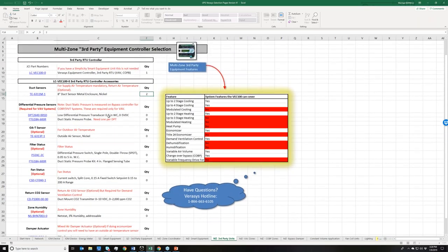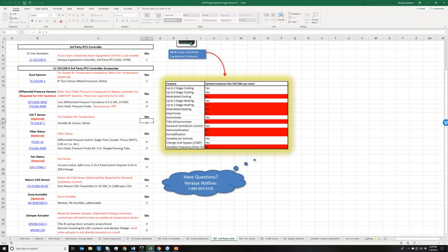Ducted pressure is measured at a bypass for a changeover bypass system with Verasys. So this is really only required for the controller if I'm doing a VAV system, because the changeover bypass system with Verasys can support both zone dampers and VAV boxes. I'm going to show an opportunity here using changeover bypass. Just note that if this was a VAV rooftop unit supporting VAV boxes with a drive on it, we would want to measure duct static pressure at this controller, and then we would have to have these sensors here. At this time, we do not.